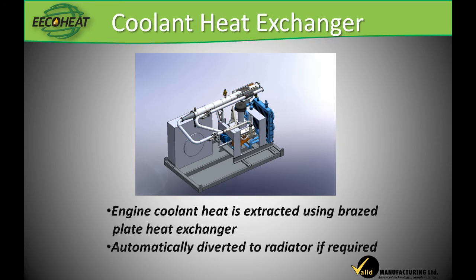In addition to heat reclaimed from the engine exhaust gases, heat from the engine's cooling jacket fluid is also scavenged in order to recover the maximum amount of heat possible. The engine glycol is circulated through a high-efficiency double-walled brazed plate heat exchanger, thereby transferring the engine heat into the high-efficiency thermal transfer fluid. Just as in the exhaust bypass system, the flow of engine coolant heat can either be directed through the brazed plate heat exchanger or allowed to simply circulate through the radiator in its standard fashion. The onboard control system determines when to include the engine coolant flow and when not to.